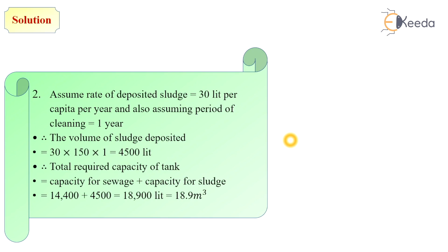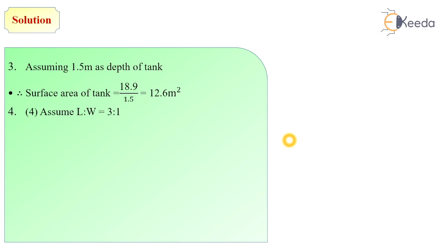The overall capacity of septic tank is 18.9 cubic meters. We assume the depth of tank, which is in the range of 1.2 to 1.8 meters — in this problem we assume it as 1.5 meters. Then from these two values we calculate the surface area of tank, which equals volume divided by depth: 18.9 divided by 1.5 equals 12.6 square meters. We assume length to width ratio equal to 3 to 1, meaning the length is 3 times its width.